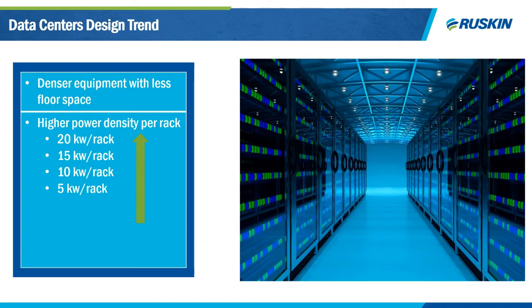Now, the trend we see with these servers is that they used to be designed for 1 kW per rack, but the trend has been toward higher power density. It's very common now to see 10 kW per rack, 15 kW per rack, and even higher. That increase in power density also increases your HVAC load.